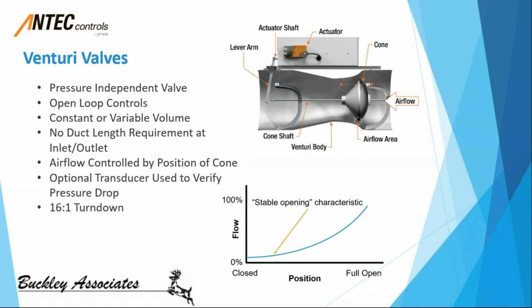So again, let's take one last quick look at a true Venturi valve. Here we have a Venturi body with a spring and cone assembly internal to the unit. Airflow in this device is not measured in any way. This device is calibrated out of the factory, and at a specific position of this control arm and the cone in this body, it is designed to allow airflow through the device between two pressure ranges. We have two different types of pressure ranges. We'll work with you when we're designing these systems to determine what valve is best. We just need to know an operating range of pressure that's going to go through this valve, and then we can design the valve perfectly to operate at certain airflows.